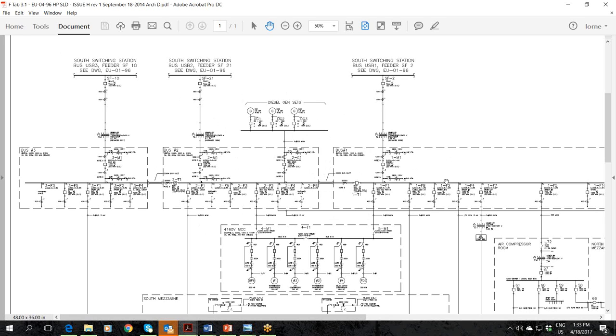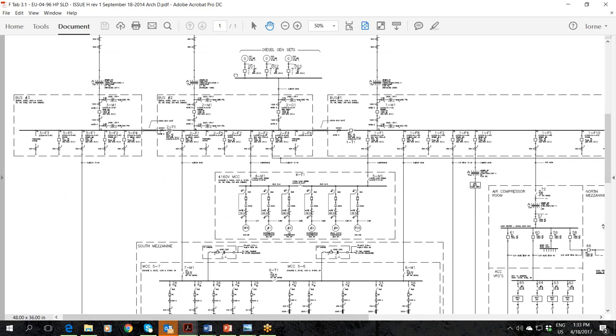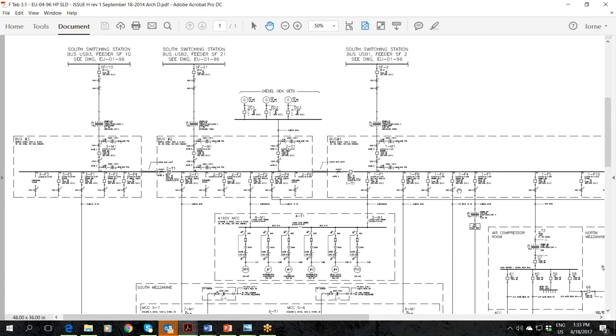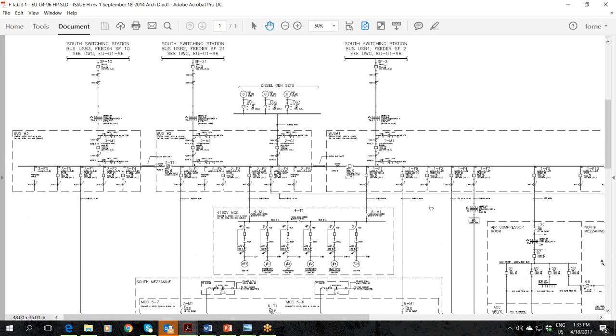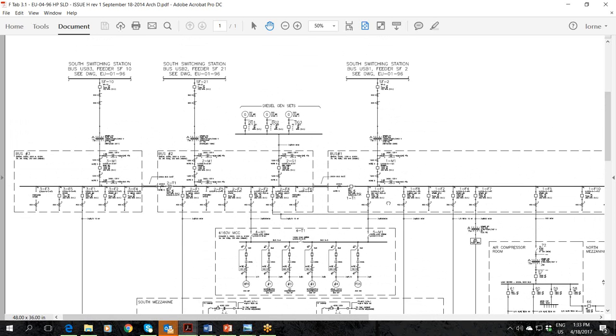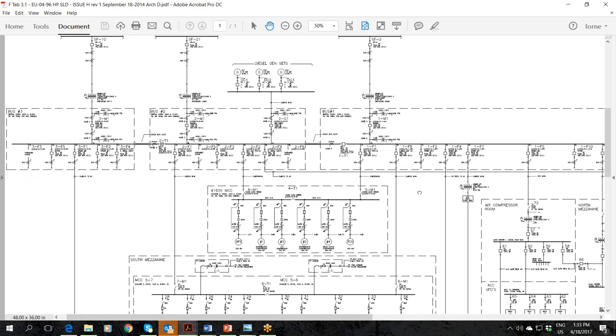Again, they're about 15 MVA, 31 MVA, so that only adds up to around 50, which is our average load, I'd say. So during the peak of summer, when we're running all these electrically driven chillers, we're not able to be self-sufficient at this time. We're talking about adding another generator down the road, but that's going to be down the road. Anyway, getting back to the heating plant.